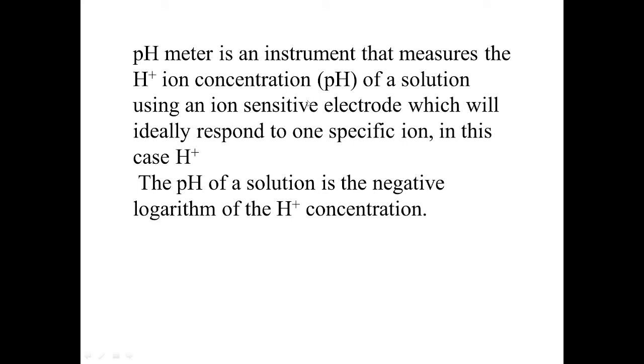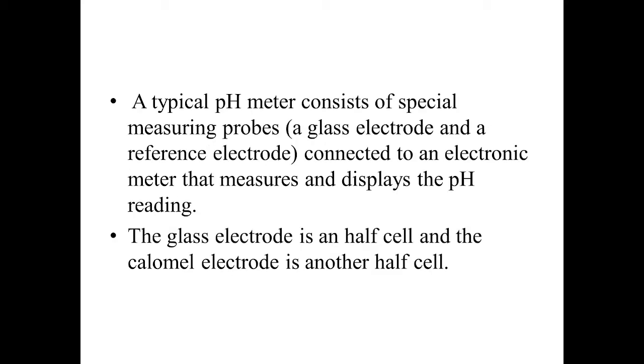Now, what is a pH meter used for? A pH meter is an instrument that measures the hydrogen ion concentration, the pH, of a solution using an ion sensitive electrode, which will ideally respond to a specific ion, here the hydrogen ion. So we have an electrode which responds to the hydrogen ion concentration of the solution and ultimately gives you the pH of the solution. What is pH? It's the negative logarithm of hydrogen ion concentration. So the instrument measures the pH.